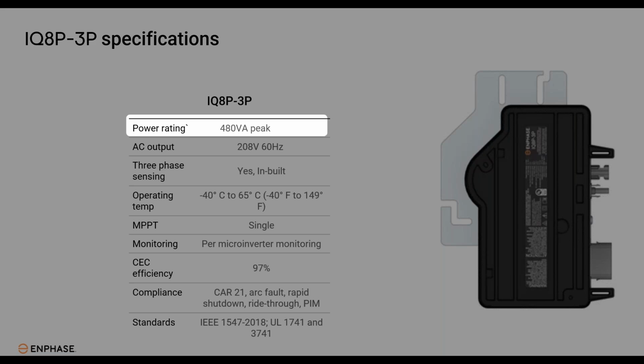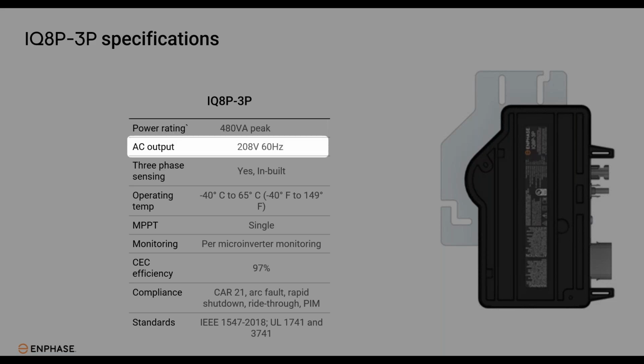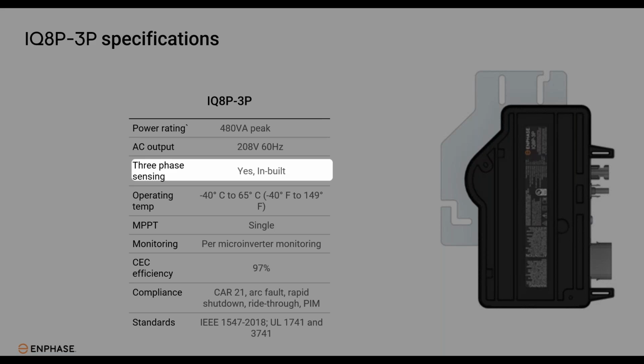Most people would just say 480, but since they are intelligent and reactive power sources that respond to site conditions, the technical way to represent that is volt amps. As mentioned, it operates on an AC output of 208 volts and has 3-phase sensing built in.